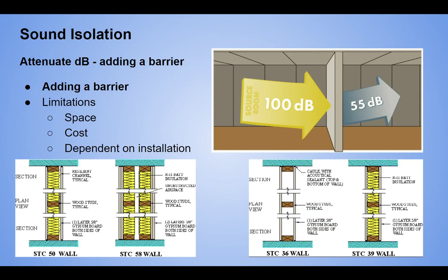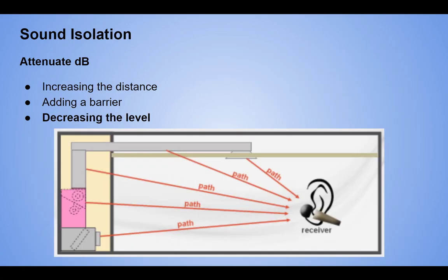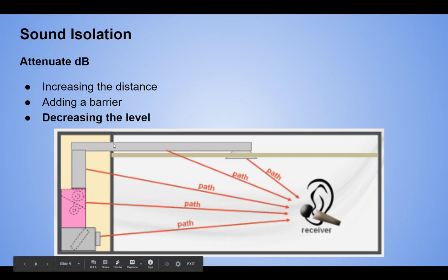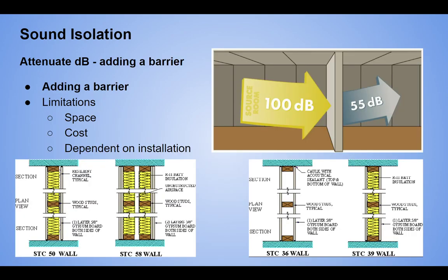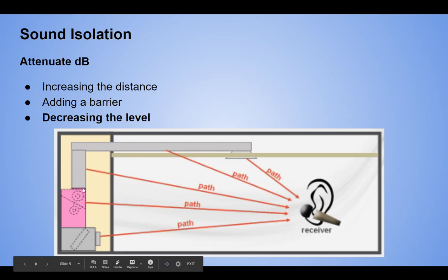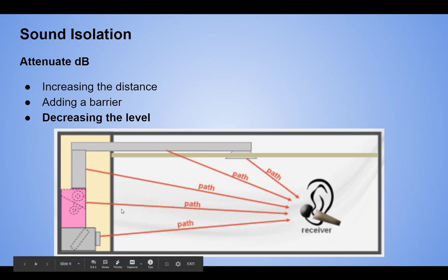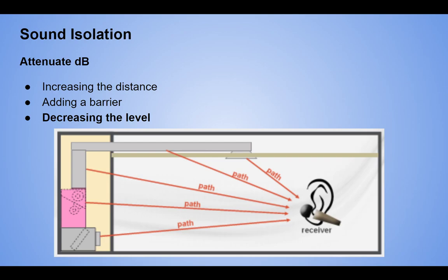Limitations of adding a barrier include space, cost, and dependence on installation. If we're at 100 dB and we can only achieve 45 dB reduction — we don't have enough room for a double stud wall. We've got to go back and decrease the level on the source side, change the noise, or move the equipment to the other side of a corridor. Now there are two walls the noise has to get through and we don't need a 58 or 60 STC wall.